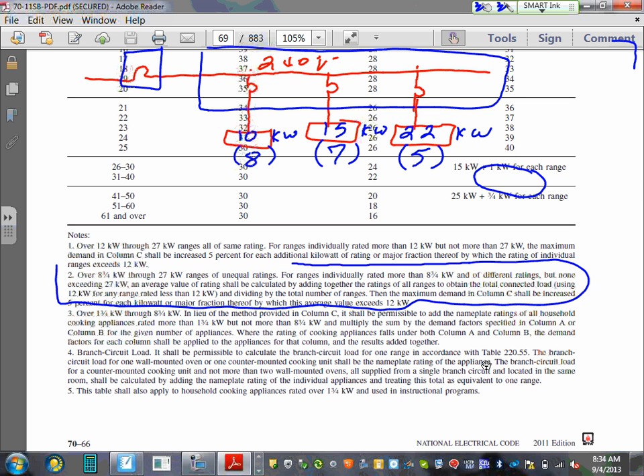If you guys read through this rule, it tells you very simply. Can you see that rule? It says if all the sizes are 8 3/4 through 27, add them up, average them, and increase the average 5% for every kW the average is more than 12. Increase the demand 5% for every kW the average is more than 12.